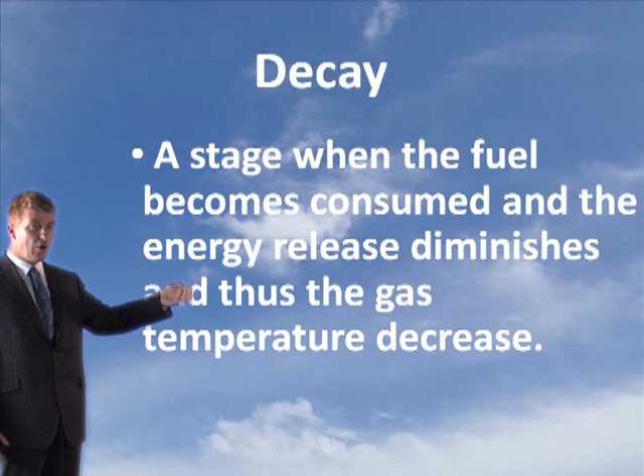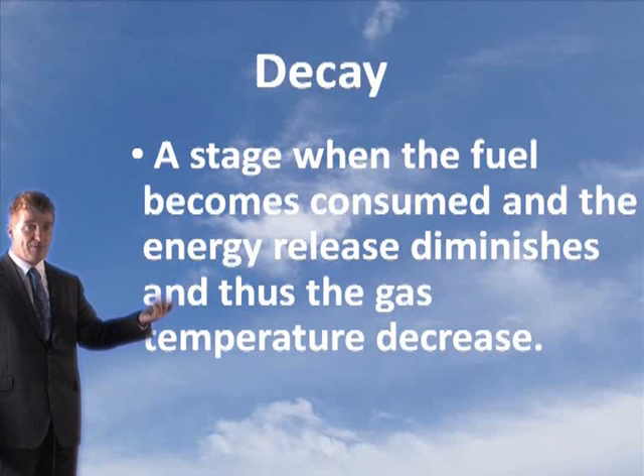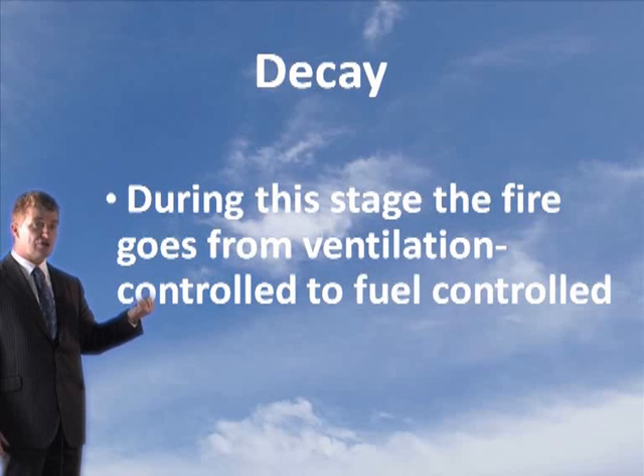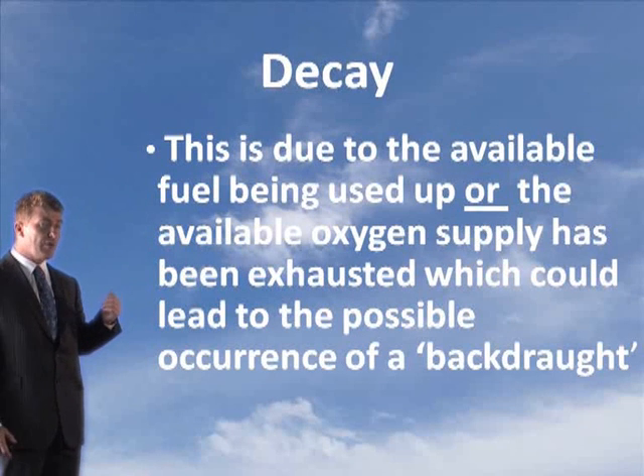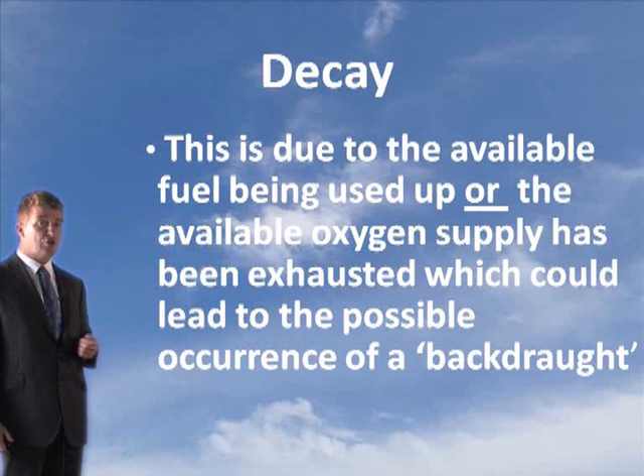If the fire starts to run out of oxygen, the temperature goes down. But if somebody opens a window or a door, what can happen is a backdraft, and the fire goes back up to a fully developed fire with another flashover. The fire goes from a ventilation controlled fire — where there's loads of oxygen — to a fuel controlled fire. It will continue burning until all the fuel is consumed or the available oxygen supply is exhausted, which could lead to a backdraft, or the intervention of the fire brigade putting water on it. Whatever the intervention or reason, there will be a remarkable decrease in the temperature and eventually the fire goes out.